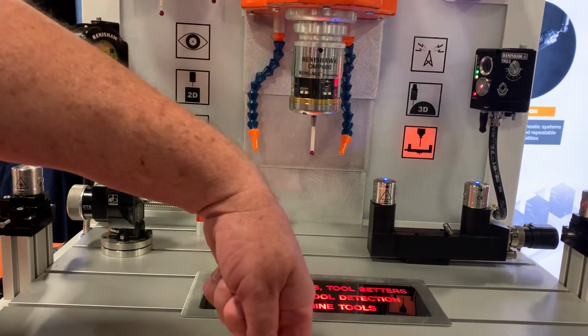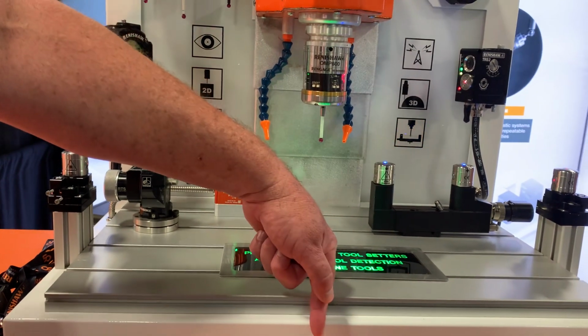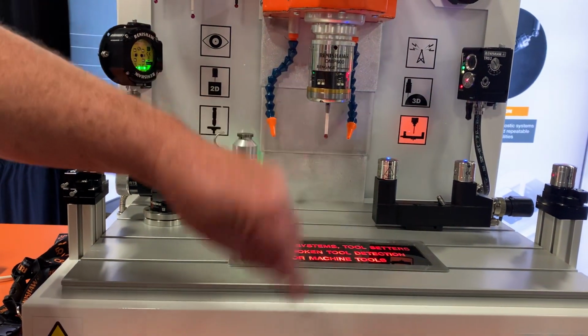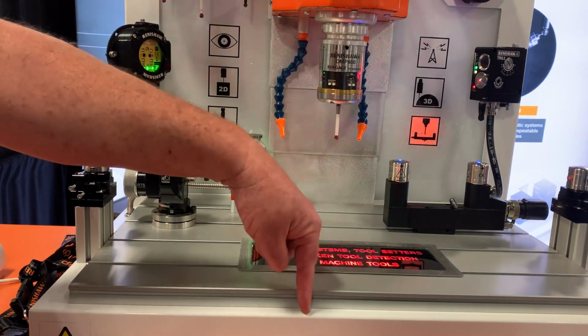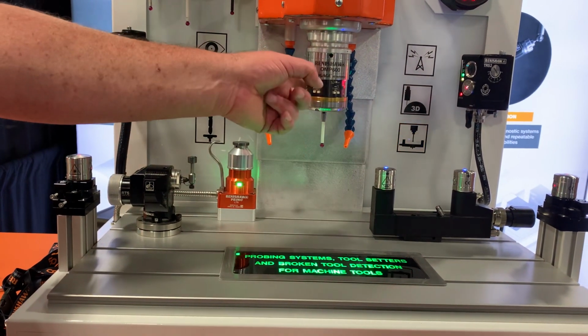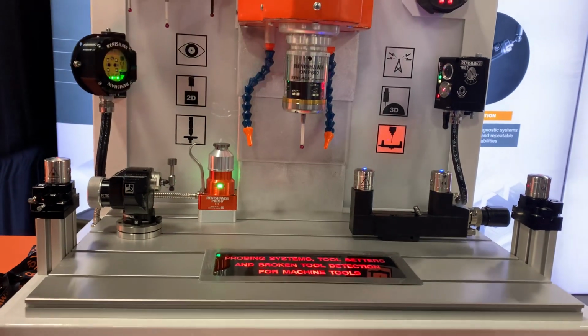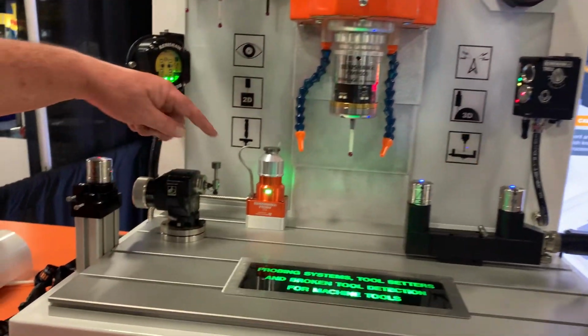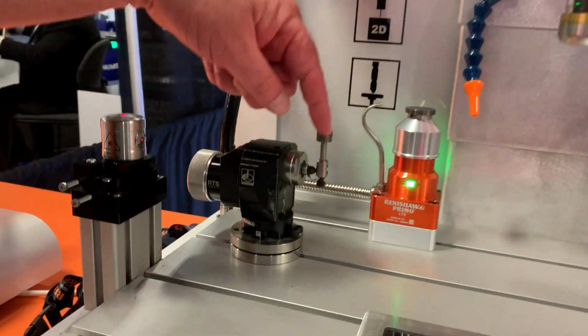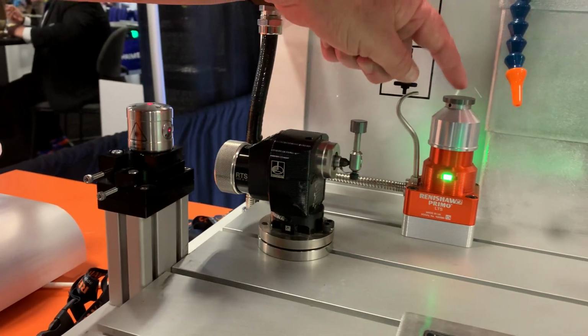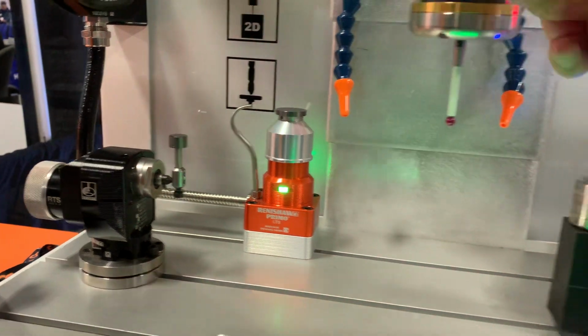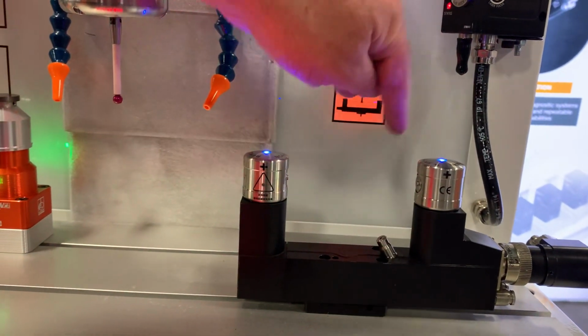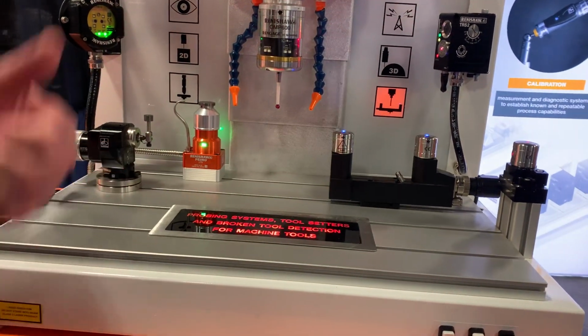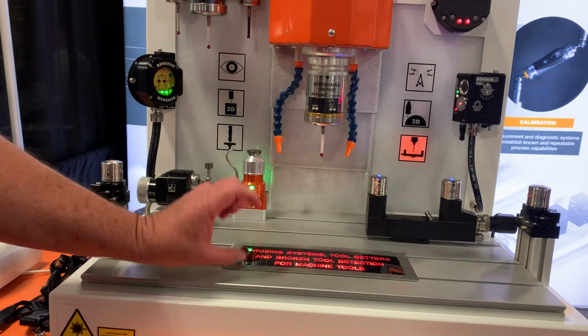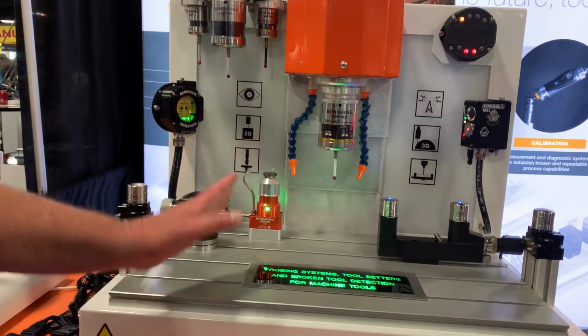The thing to keep in mind is that when the probe triggers, it freezes the position the machine thinks it's at. But if you've calibrated your machines, you know they're going to the right spot. So then you can do inspection with the probe on the machine after you calibrate it. And then we have different tool setters. We have a touch tool setter where we can touch here and get the diameter of the tool, but we can also use this plunger to touch, or we have lasers that we can go through here, or they can span all the way across. So we can do break detection. We can come in and just touch before it goes in, any of the above, to help control your process.